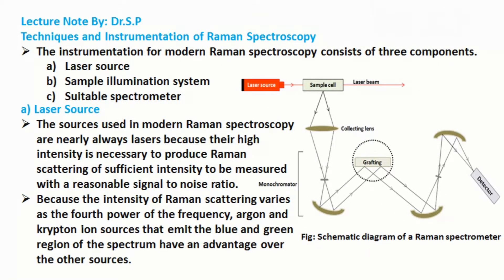The instrumentation for modern Raman spectroscopy consists of three components: a laser source, a sample illumination system, and a suitable spectrometer. The sources used in modern Raman spectroscopy are nearly always lasers because their high intensity is necessary to produce Raman scattering of sufficient intensity to be measured with a reasonable signal-to-noise ratio. Because the intensity of Raman scattering varies as the fourth power of the frequency, argon and krypton sources that emit in the blue and green region of the spectrum have an advantage over other sources.